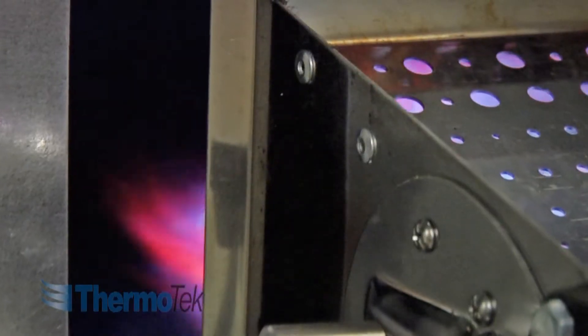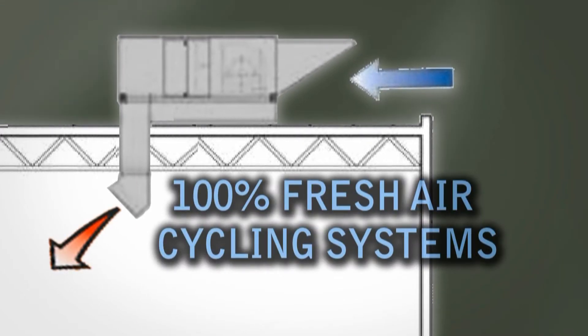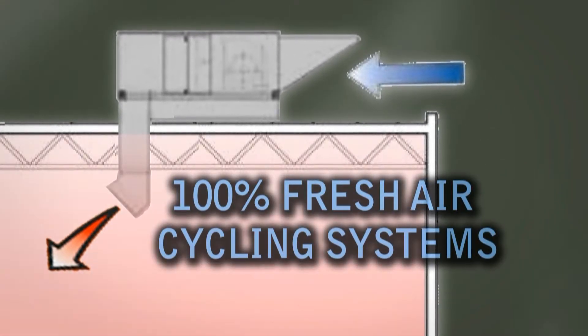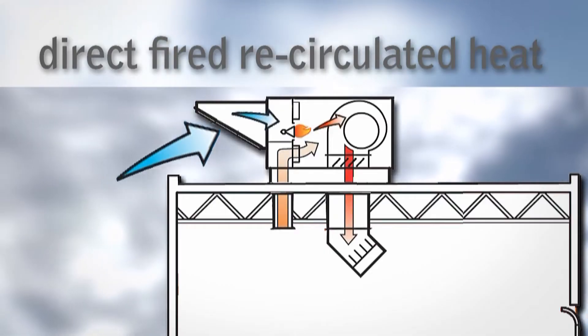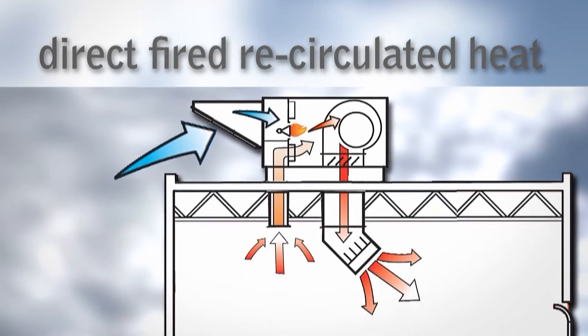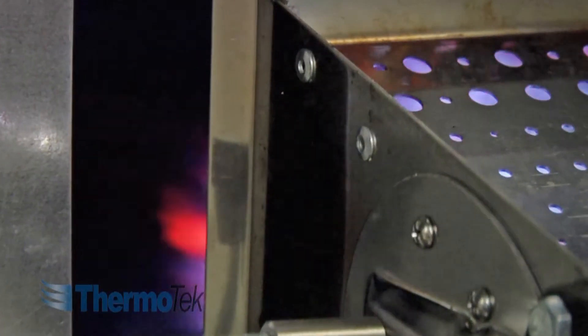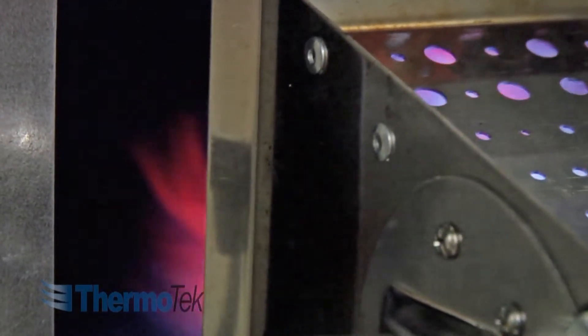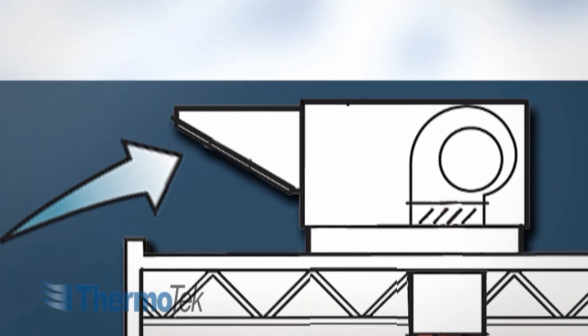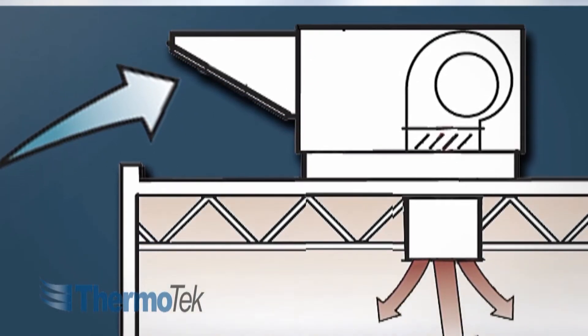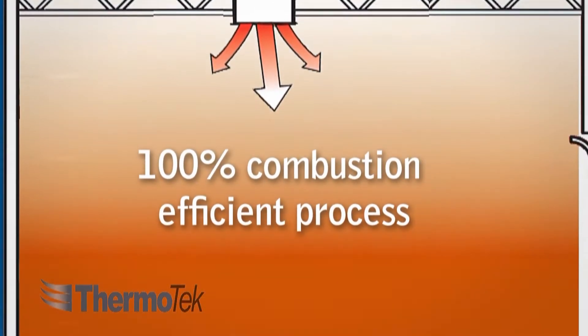When using direct heating methods, such as direct radiant heat, 100% fresh air high temperature direct fired systems, and direct fired recirculated heat systems, all of the heated energy is conserved by safely introducing it into the space. Direct fired refers to heating equipment that burns gas directly into the fresh air stream, resulting in the most efficient method of heat transfer and is a 100% combustion efficient process.